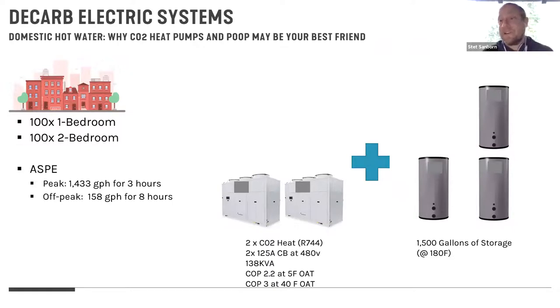The nice thing about CO2 heat pumps is that they are able to actually produce 180 to 197 degree water, which is fantastic, especially for domestic hot water. And they're able to do that even at really low outside ambient air temps. And you get a pretty good COP, even at those low temps, and phenomenal COPs in moderate outside air temperature.